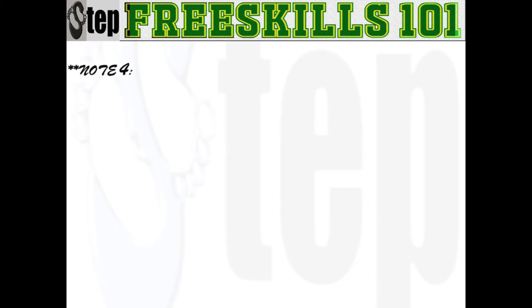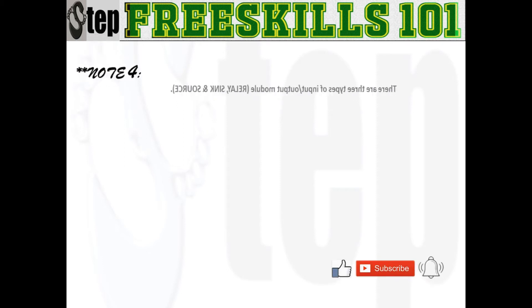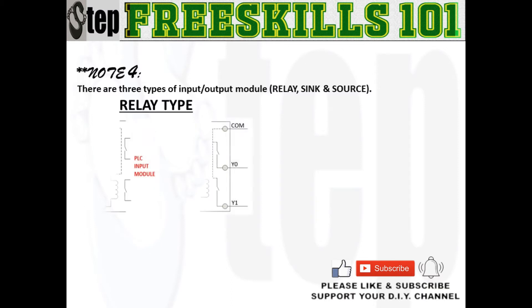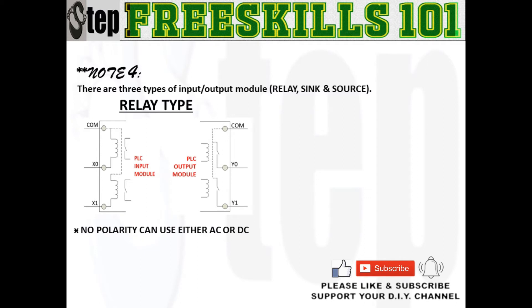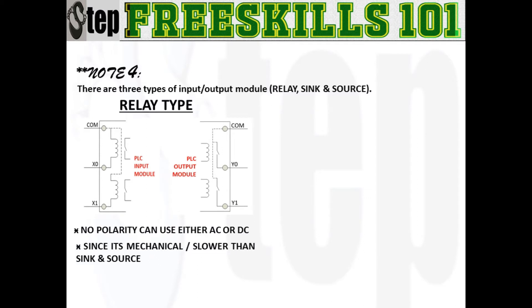There are three types of input and output modules and they are relay type, sink, and source. Relay type has no polarity since it is a mechanical type. You can wire either an AC or DC circuit, but like any electromechanical type such as solenoid relays, it is slower and prone to mechanical drift.